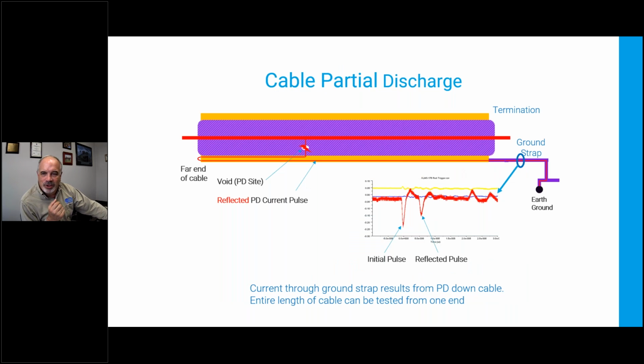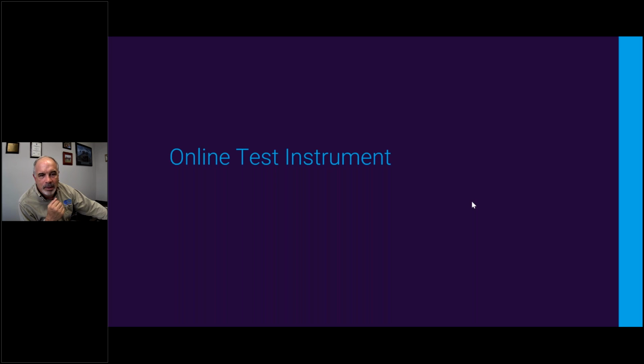Nice thing with cable discharge is I can look at the ground strap. Discharge goes from the conductor to the ground strap if it's inside the shielded portion. If it's outside the grounded portion, the current is still traveling down the conductor. The conductor acts like an antenna, and it radiates into the shield and goes down the ground strap. So if I can count the electrons going down that ground strap, then I can determine whether I've got PD or not.